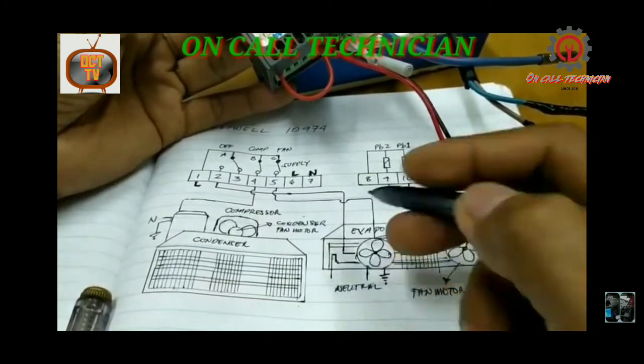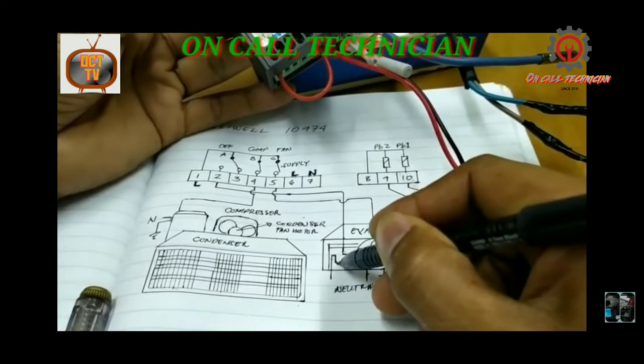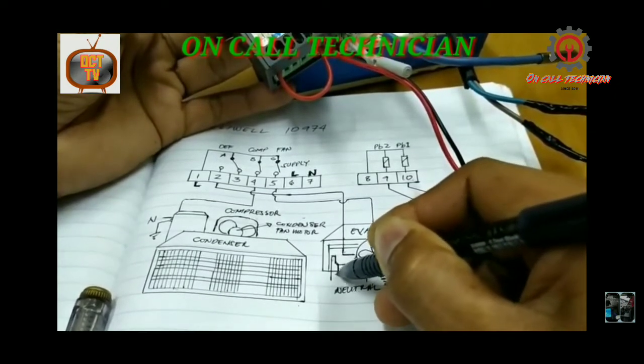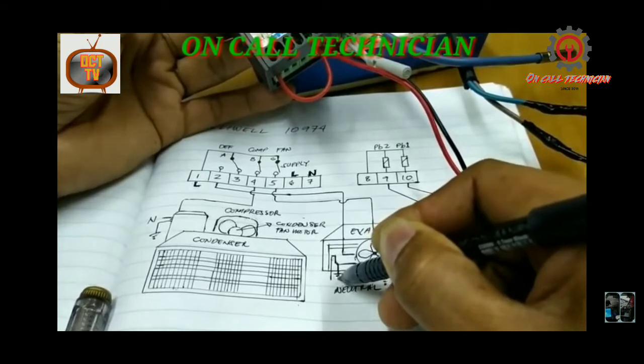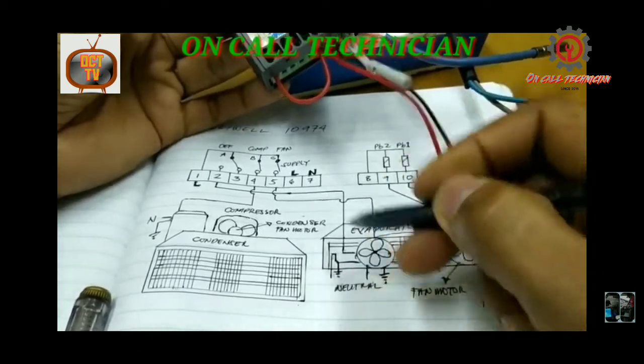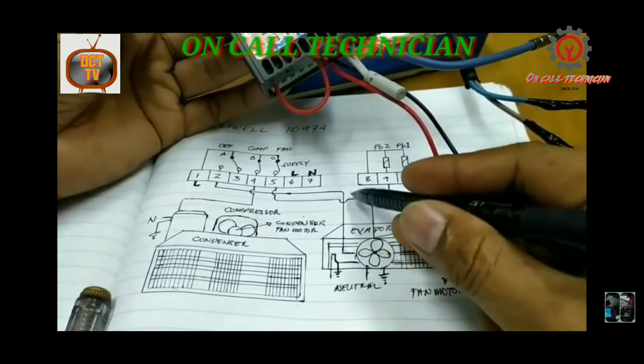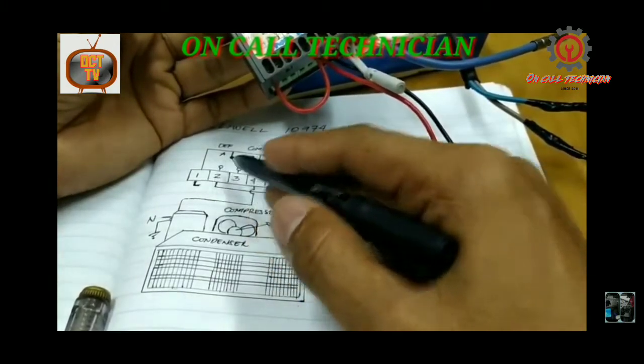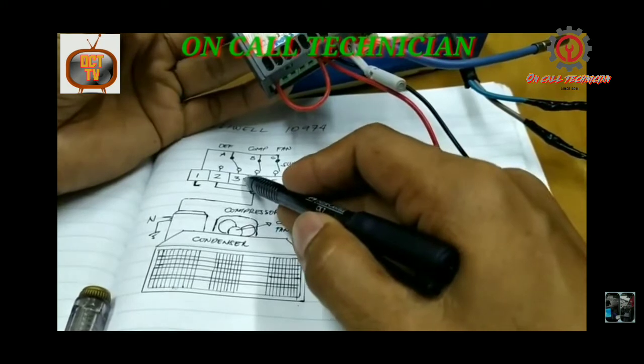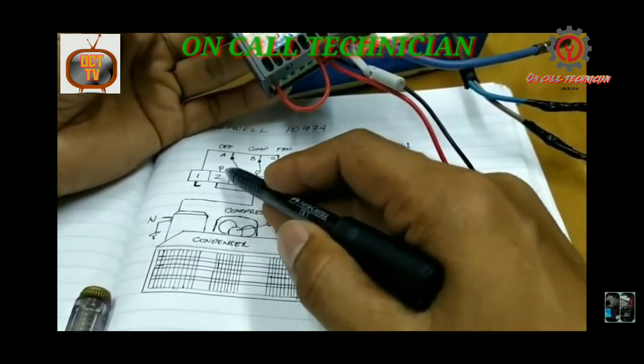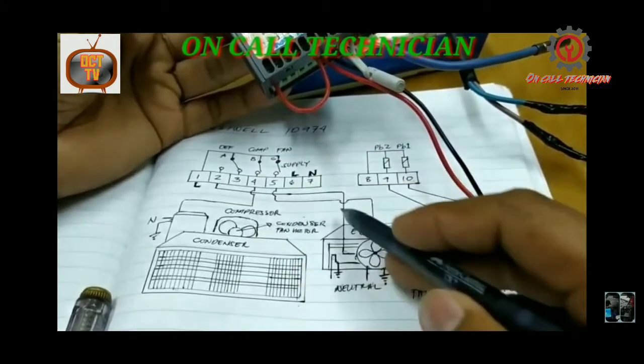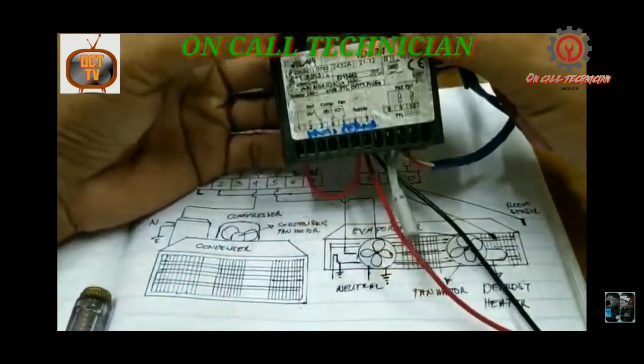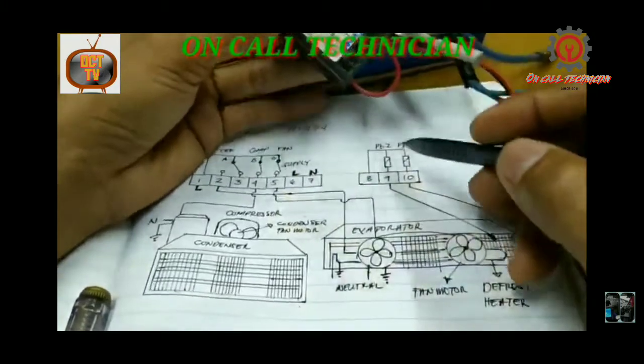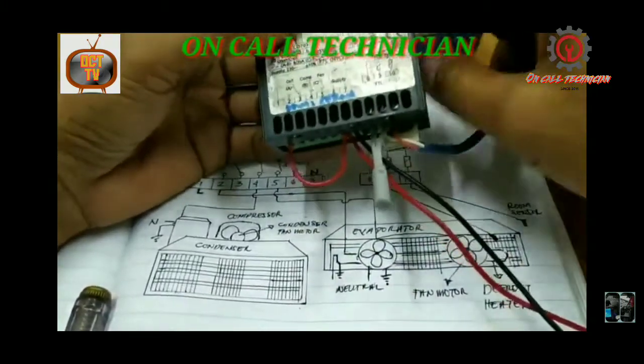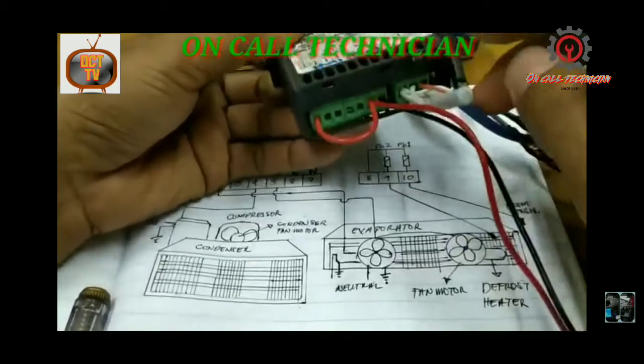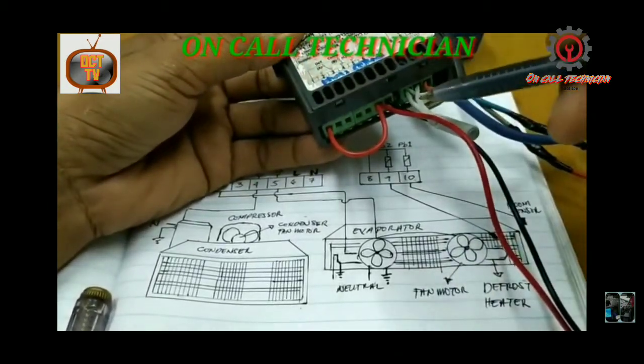Take note. You can reach me, so just listen to what I say here. So this is our defrost, under the evaporator is the defrost, guys. The defrost also has ground and neutral, and you tap it to terminal number 2, not to terminal number 3, guys. If you tap it to terminal number 3, both the compressor and evaporator fan motor will run together with the defrost heater. So don't be confused. Plug it into terminal number 2.